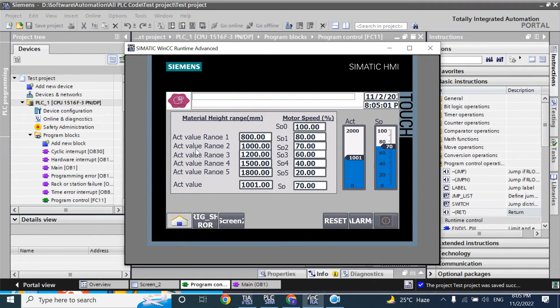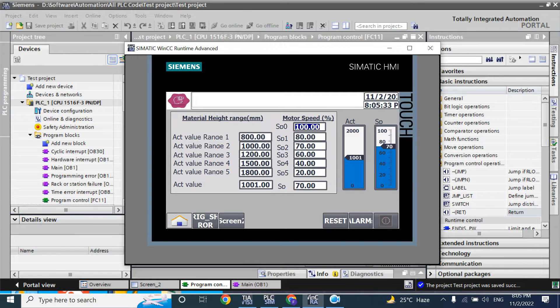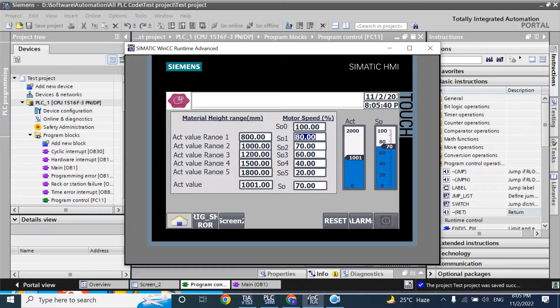Our target is that the material height in a bunker we want to maintain. If the material height is less than 800 mm in a bunker, then the motor will take the speed 100% to bring more material. If the material height is in between range 1 and 2, we will take the speed SP80 — 80%. If the actual value is in range between 2 and 3, then speed will take 70%.